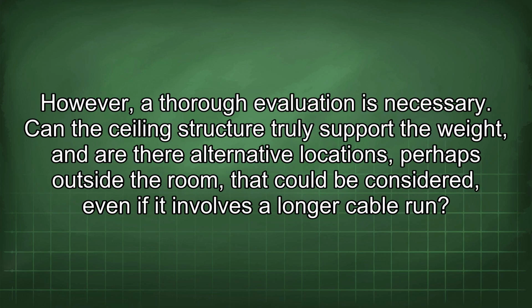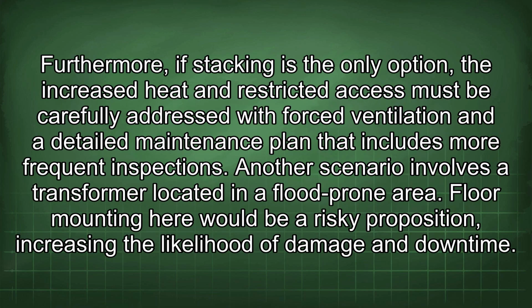However, a thorough evaluation is necessary. Can the ceiling structure truly support the weight, and are there other alternative locations, perhaps outside the room, that could be considered, even if it involves a longer cable run? Furthermore, if stacking is the only option, the increased heat and restricted access must be carefully addressed with forced ventilation and a detailed maintenance plan that includes more frequent inspections.